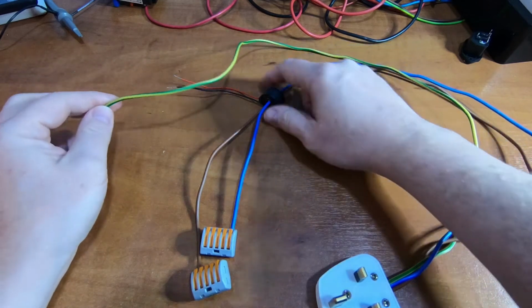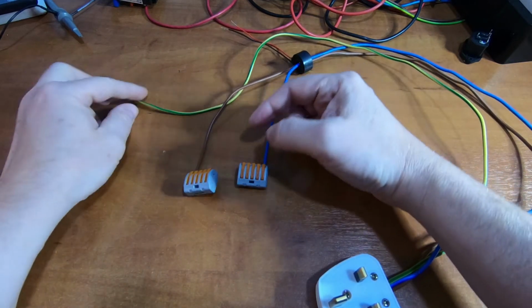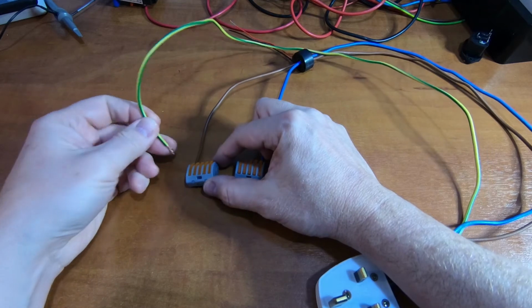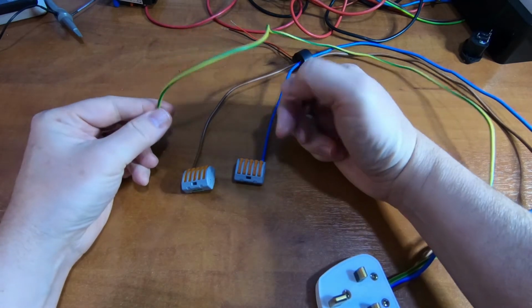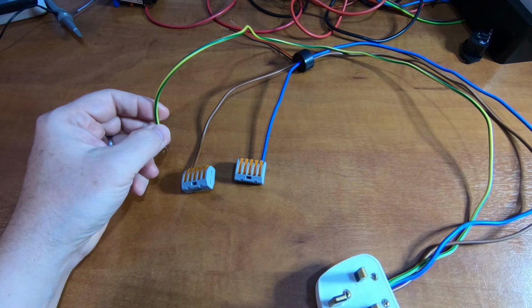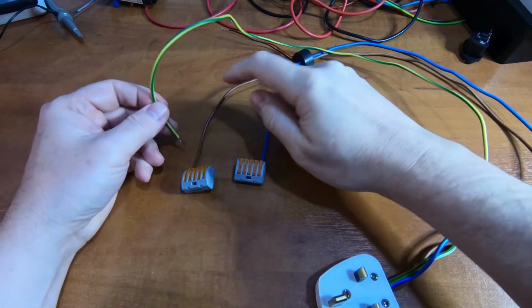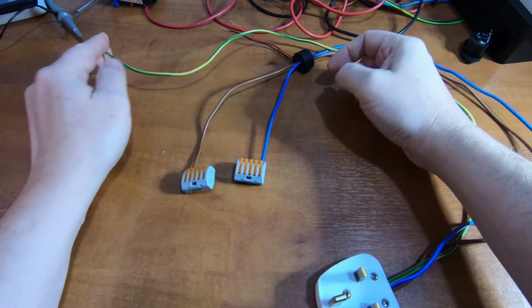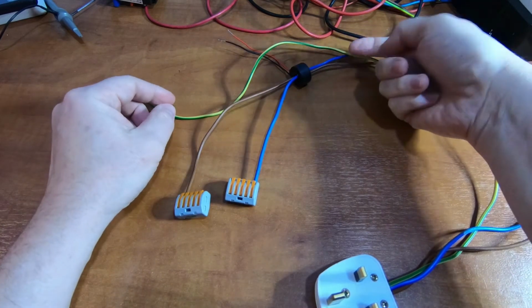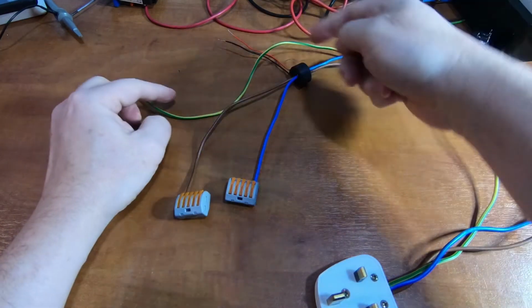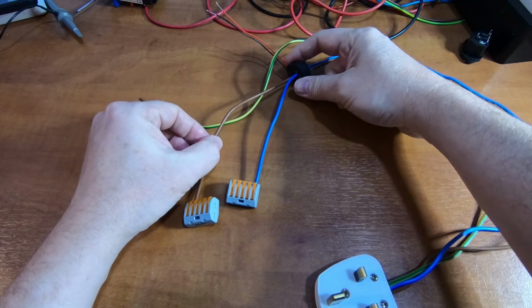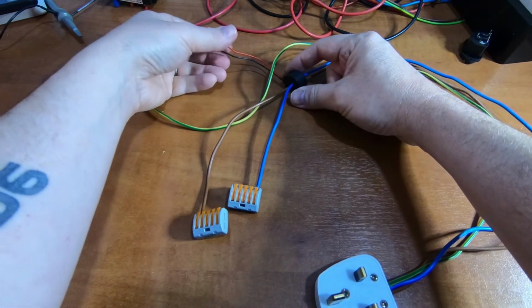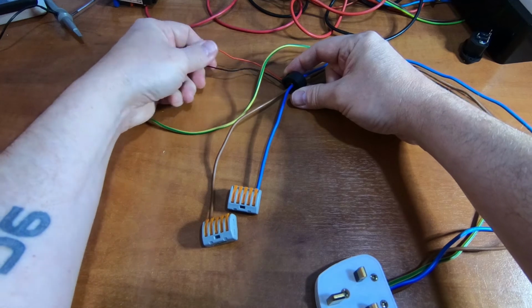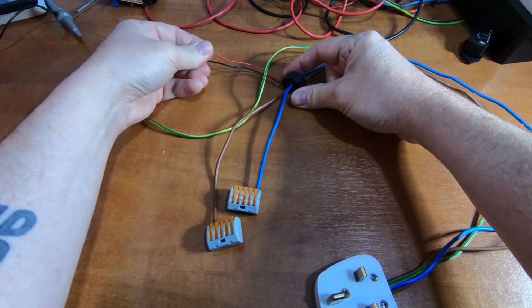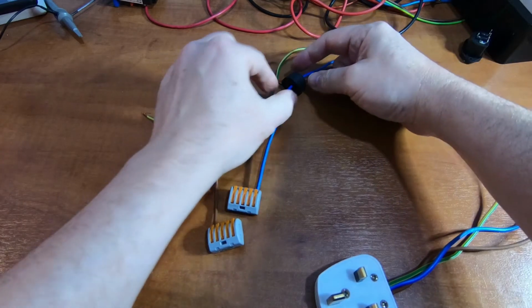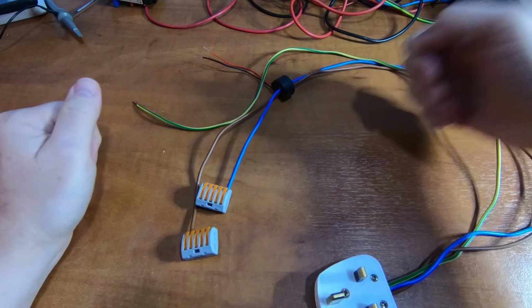So this test here, what I'm going to do is just put the earth to live via a suitable resistor, and that is going to generate a current back through the earth lead. The current will come through the live and back through the earth, and this current transformer is going to pick that up and detect it, and we'll see an AC voltage on the secondary of the current transformer. The primary, of course, is the conductor that's through the center.